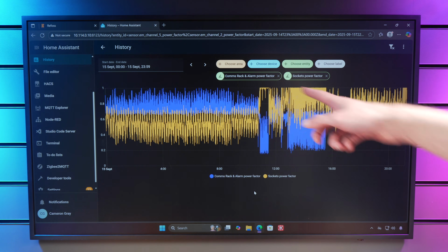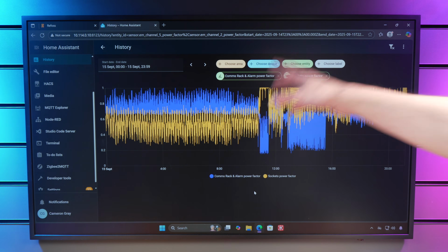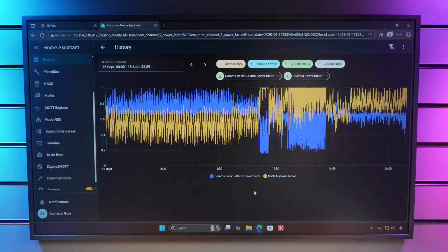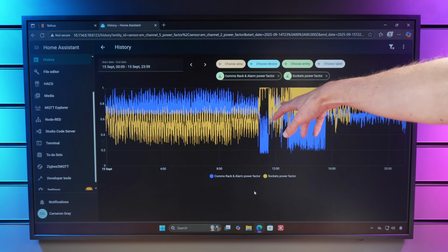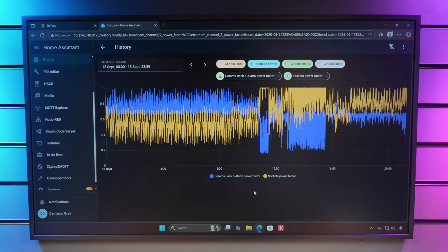Then what happened is, round about this time here this morning, I switched on the washing machine onto a wash-dry cycle. Now a washing machine has a very big resistive heating element in it, and that was plugged into the socket circuit. So because it's a resistive heating element, anytime the heating element comes on, that will massively change the power factor of the socket circuit to go much closer to 1, because we've got a big resistive load there. And you can see, if you look at the socket circuit, it does.